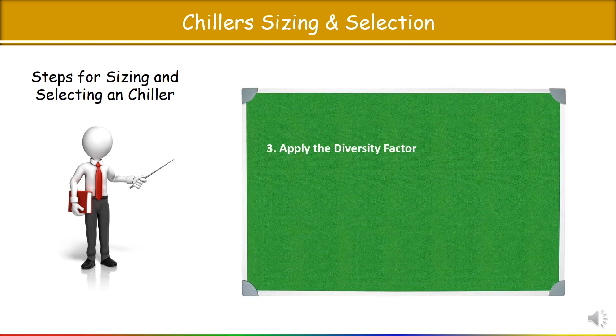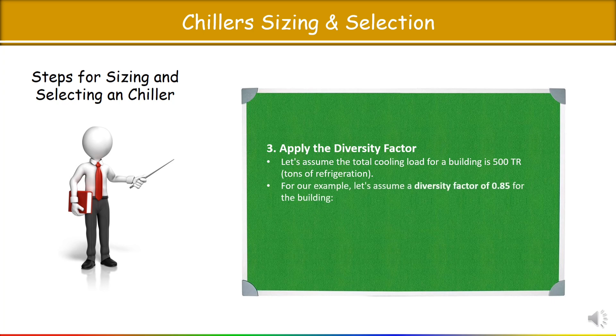The third step is to apply the diversity factor. Let us assume the total cooling load calculated from HAP software or any other software or manual calculation is 500 TR — ton of refrigeration. For example, we are considering a diversity factor of 0.85 for the building, depending on the building type.